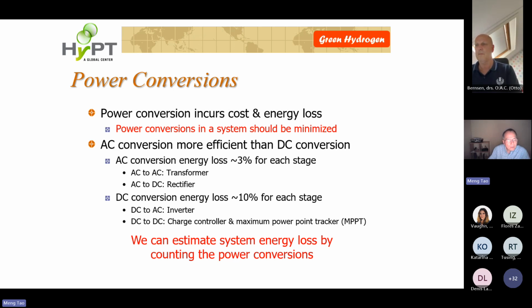In this case, we will have both AC conversions and DC conversions. AC conversions, such as AC to AC through a transformer or AC to DC through a rectifier, are typically much more efficient than DC power conversions. So here I use 3% loss for each AC conversion, and 10% for each DC conversion, because DC conversion is based on transistor switching — for example, a DC to AC inverter, a DC to DC charge controller, or a maximum power point tracker.